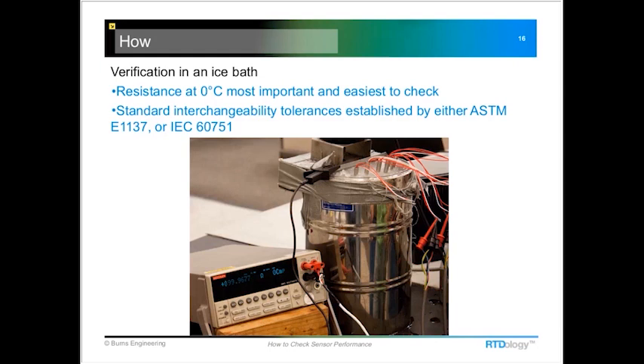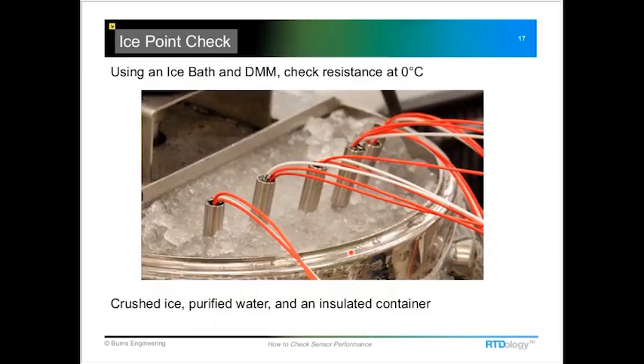If you have a lot of fancy equipment like this multi-decimal place meter here, which does the lead wire compensation automatically, that's great. A nice stainless steel dewar here, and this one actually has a stirring motor in it that circulates the water throughout the ice to give you even a little better accuracy. But really, to do a quick verification, you don't need a whole lot of fancy equipment. Mostly the important part is to use crushed ice, purified water, and some sort of insulated container.